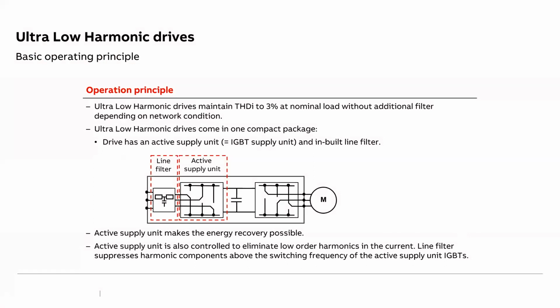So there are a lot of advantages, like it saves space. It is very easy to use, install, and commission, because it's just one box with 3 wires in, 3 wires out. No complex circuits are involved, no mechanical disturbances or further losses are involved in this. So it's a very easy and very efficient solution, and with this we can achieve the highest level of harmonic mitigation, which is bringing down the harmonics to 3%. So this is possible with these ultra low harmonic drives. Then there are many other advantages also, which we'll see now.